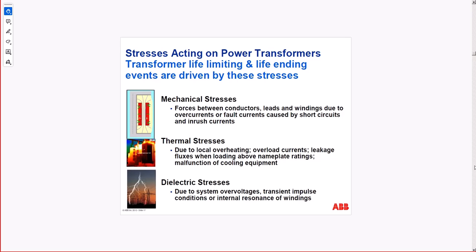No? Stress acting on power transformers: mechanical stress. When do we stress the transformer mechanically? Anytime we energize the transformer, we have forces between the windings that are proportional to the square of the current. So mechanical stress is huge at any energization. Remember, the inrush current can go up to even 21 times. In the ETAP calculation we have 12 times, but it is actually higher. Thermal stress, so that energization. Also any short. Clearly, if you have a short circuit, that will act as a mechanical stressor as well. Whenever you create high currents in the windings, that ends up in a high mechanical stress.